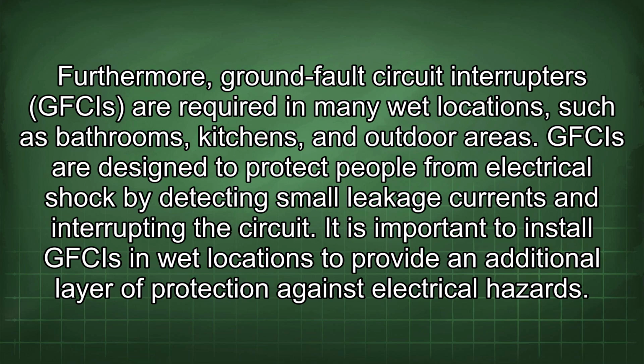Furthermore, ground fault circuit interrupters (GFCIs) are required in many wet locations, such as bathrooms, kitchens, and outdoor areas. GFCIs are designed to protect people from electrical shock by detecting small leakage currents and interrupting the circuit. It is important to install GFCIs in wet locations to provide an additional layer of protection against electrical hazards.